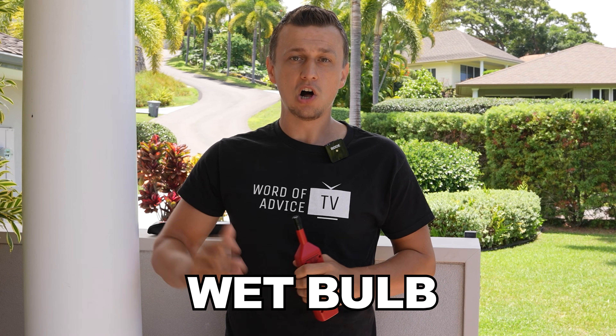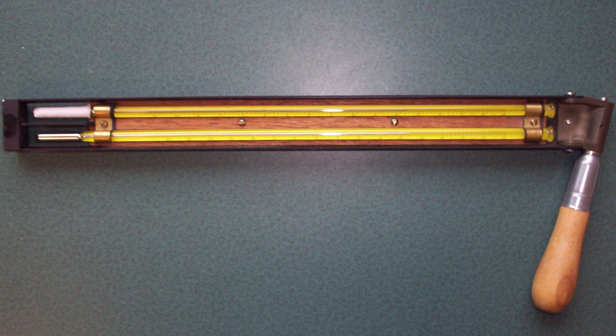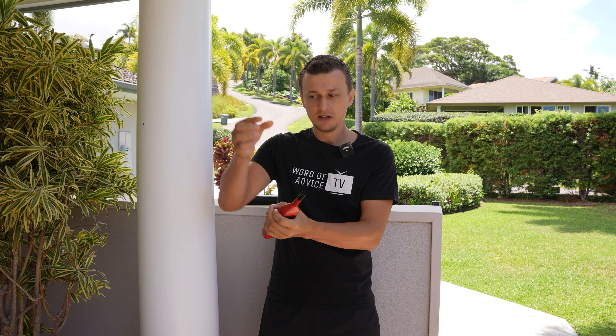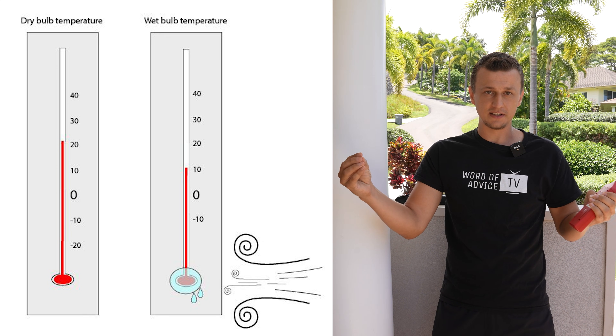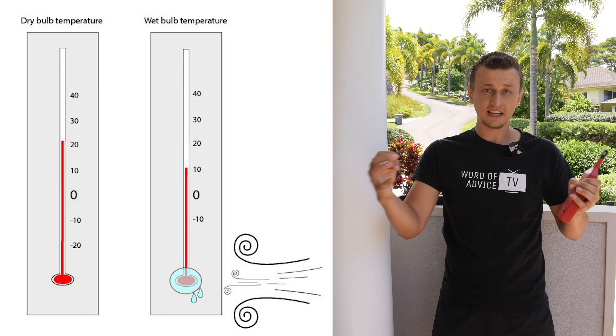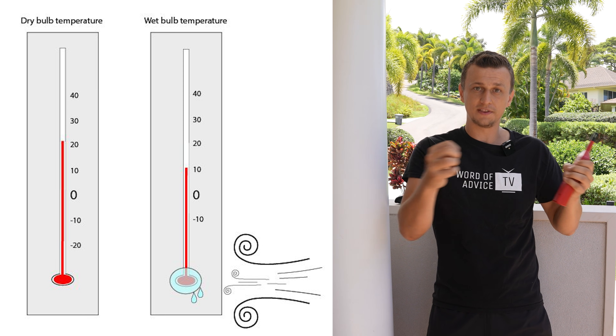As for wet bulb temperature, it will almost always be lower than the dry bulb temperature because it also considers evaporation. The easiest way to understand this is to look at how they measured wet bulb with sling psychrometers. Basically it's a regular thermometer with a little sock of cloth over it, dipped in water and swung around like nunchucks. That swinging motion causes the water in the cloth to evaporate, and as it evaporates it takes some of the heat from the metal probe with it.